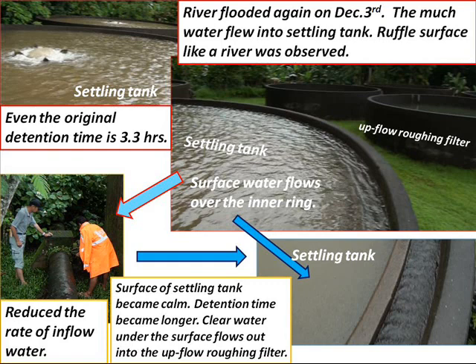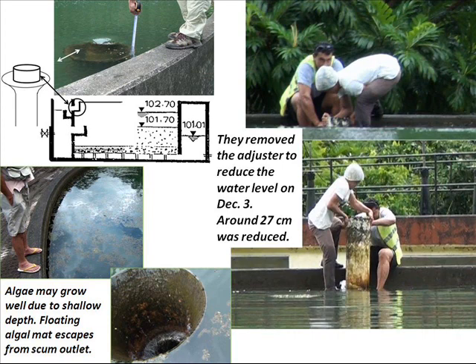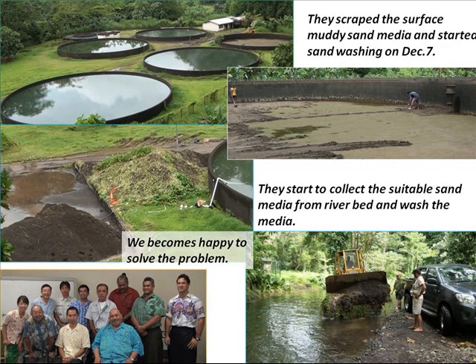We reduced the rate of inflow water. The surface of the settling tank became calm and detention time became longer. Clear water at the surface flowed out into the upflow roughing filter. They removed the adjuster to reduce the water level by around 20 cm so algae could grow well due to shallow depths. Floating algal mat escaped from the scum outlet. They scraped the surface muddy sand media and started sand washing, then began collecting suitable sand media from the riverbed.